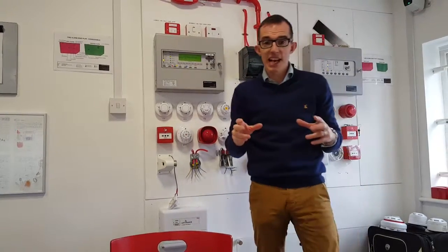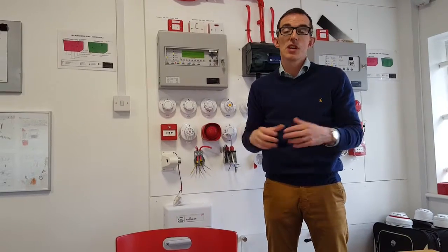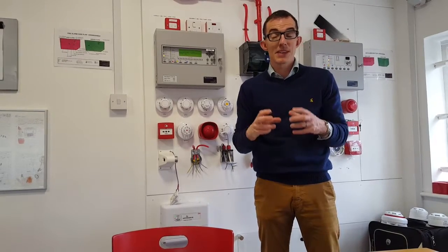You then have to test how the system would work under alarm conditions, so you have to ring the bells or the sounders, and then finally you have to test if there's specific things that operate when the fire alarm goes off, and that's called cause and effects. In essence, when you're a fire alarm service engineer, you're testing 4 things.